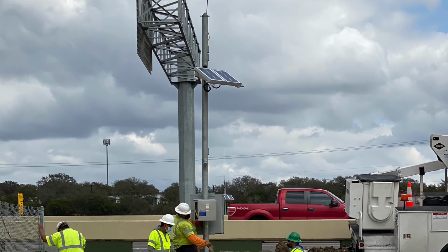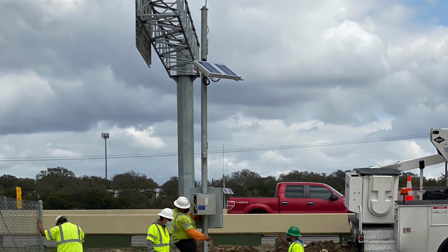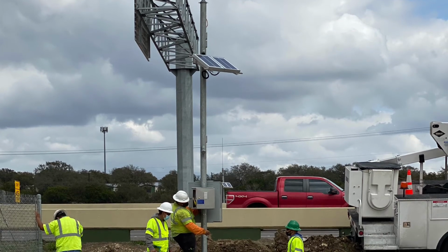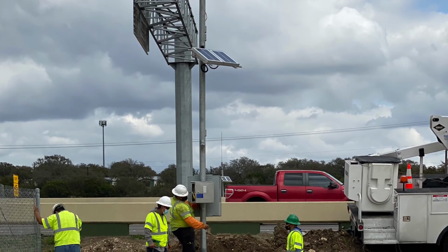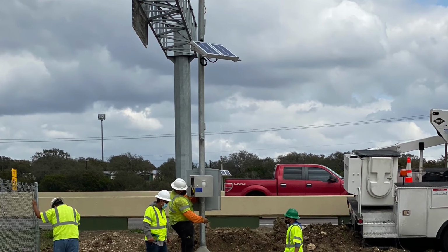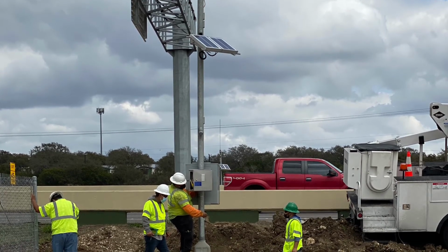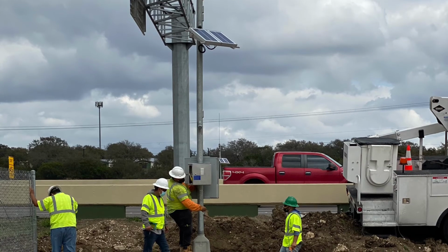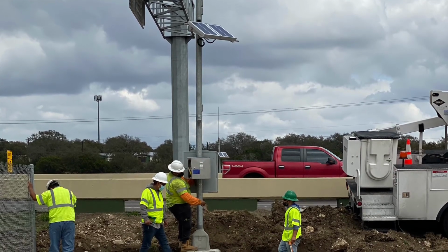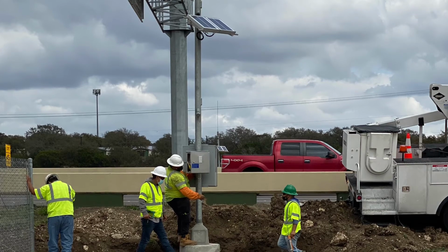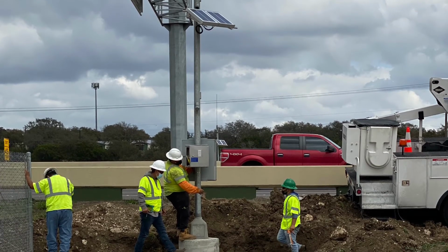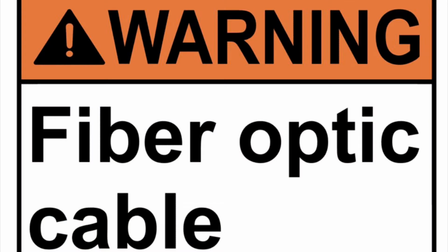Traffic management systems are a somewhat newer system being used in public transportation, but are becoming more commonplace. These systems require a significant amount of underground work, which includes ground boxes. Fiber optic cables are used in most traffic management systems, but it is very important to note that the equipment also requires power from an electrical service source, which would be installed by Levy underground crews. It's also important to note that fiber optic cables can be an expensive cable to install, especially when they have splicing requirements, and only qualified personnel can and should install and splice fiber optic cables.